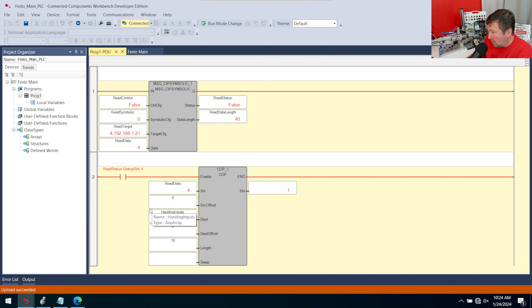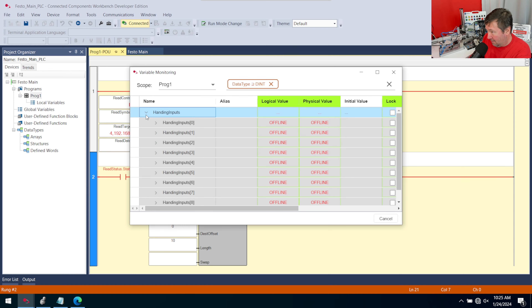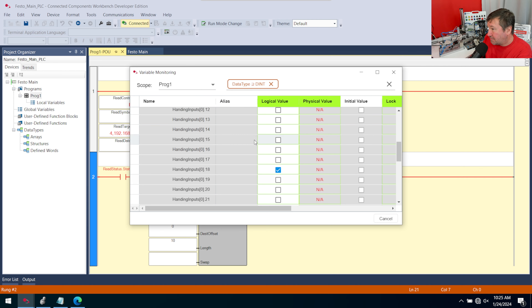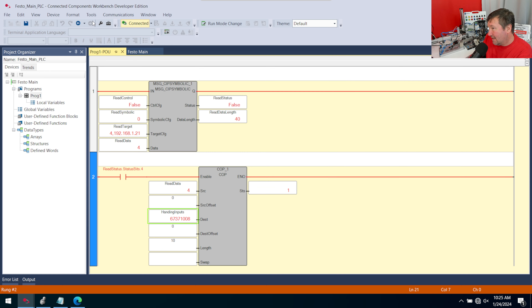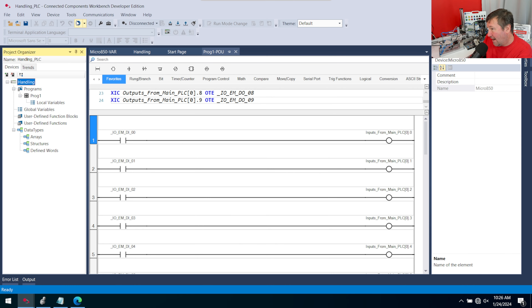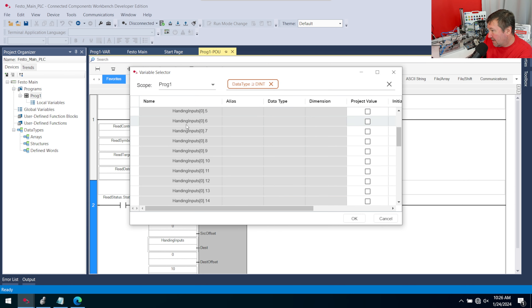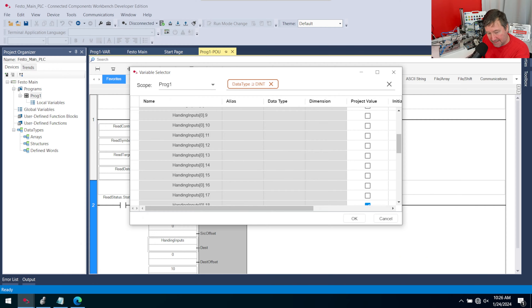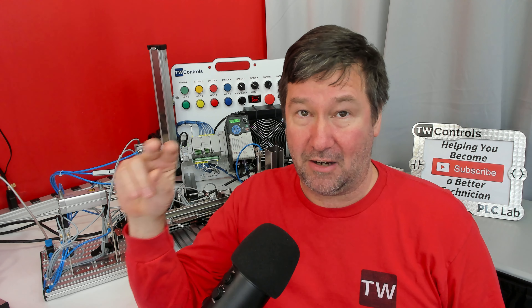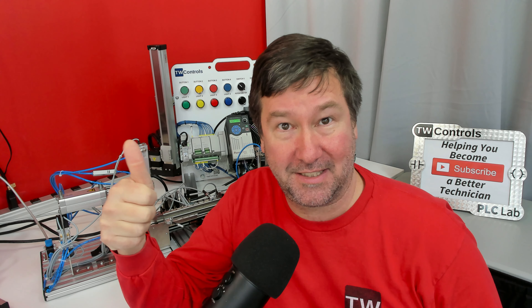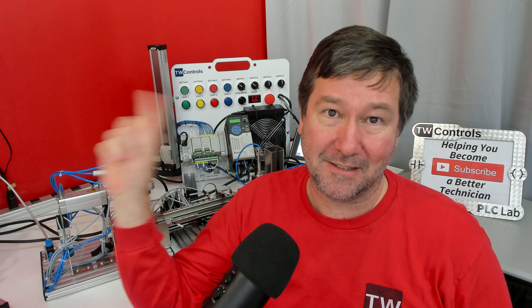Download that and now we have data in our handling inputs. But notice the number is much higher than expected. Double-clicking and opening the array shows data is in the 18th bit rather than the second bit. Comparing with the handling PLC, it's actually the second bit there. What's happening is the PLC is swapping the first 16 bits with the second 16 bits. We can fix that, but this video is getting long and there are two more major points — how to fix the bit swap and a discussion on read versus write messages. A playlist with both topics is linked.